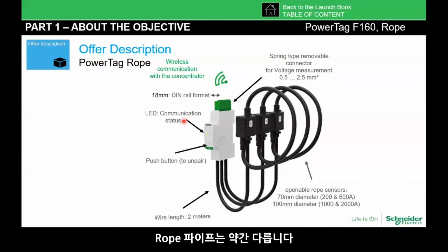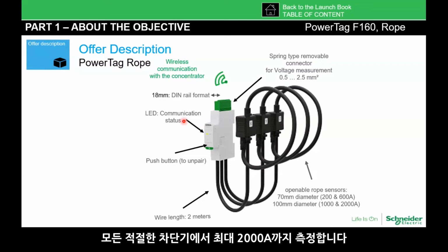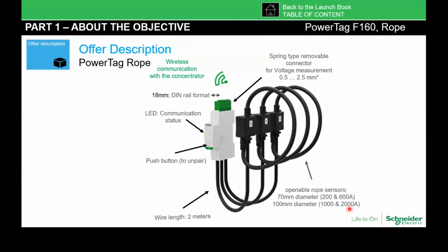Then of course the rope type is a bit different. Rope type is basically using a flexible rope, like a Rogowski coil kind of rope, where we can measure up to 2000 amp breakers. So there's flex and there's rope—flex is always limited to 160 amp, rope is up to 2000 amp.